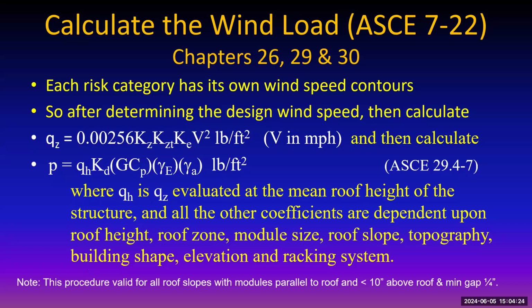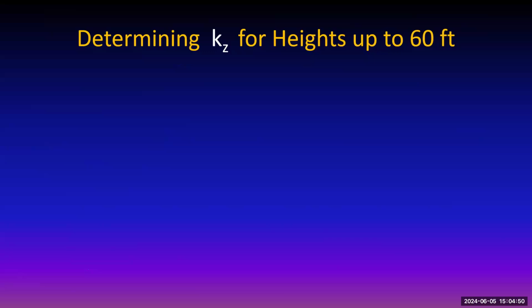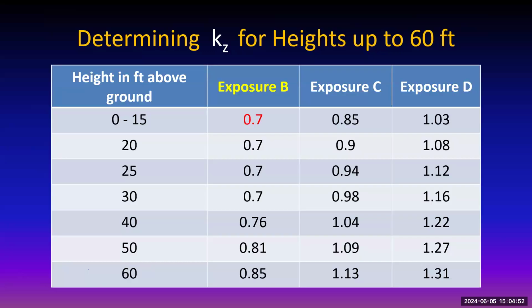All right, and this particular procedure is valid for all roof slopes with modules parallel to the roof and less than 10 inches above the roof, and a minimum gap between them of 1/4 of an inch if there are more than 2 in a row. Okay, so there are certain conditions under which these can be used, and others you have to find a different way to do it if you don't meet these conditions. So how do you determine KZ? You just look it up.